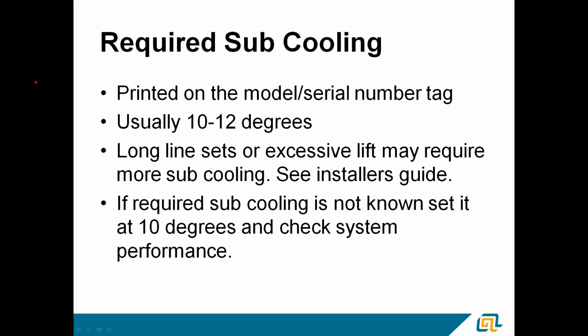If you've got a really long line set, especially a line set that has excessive lift, like you're lifting up to an attic, to an air handler in an attic or something like that, you may have to add a little bit of subcooling to it. What will happen is you'll actually run out of subcooling. The refrigerant will begin to flash in the line, and that'll throw the valve totally out of skew. If it sees bubbles coming back, if it sees flash gas coming back, it really doesn't know what to do. It will usually drive closed and act like a restricted TXV.